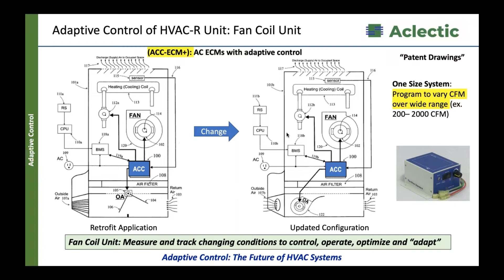What that also highlights on the right is what others are doing - instead of a damper, why not put another fan in? A fan that can be co-controlled so the outside air isn't just passive or opening, but can be modulated depending on needs or conditions. So there are multiple functions well beyond just controlling the fan motor, the EC motor - many other things that this box does.